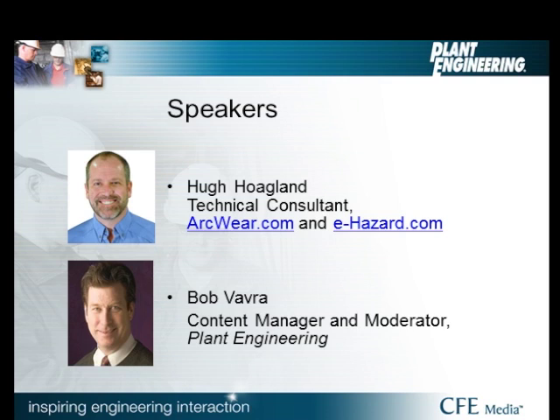But they're extremely effective, whether arc flash relays or current limiting fuses. Each of these technologies has its place. We always encourage people to be careful about a company that only sells one technology selling you the one that works for them, because it might be the most expensive option. We find in some cases current limiting fuses are much cheaper to operate. In other cases, putting in an arc flash relay is much more reliable and can lower those energies just as effectively with very little cost long term.